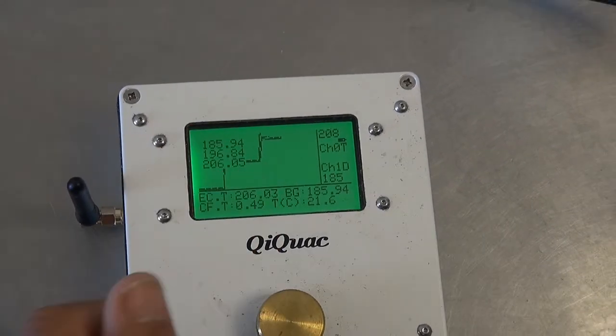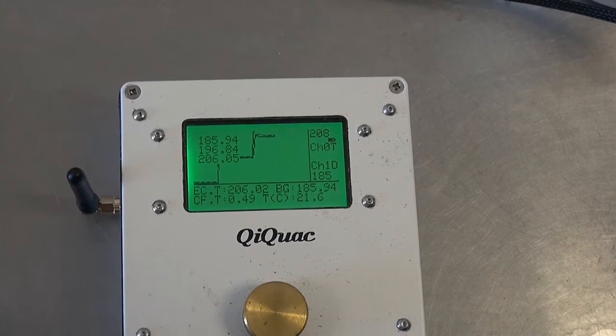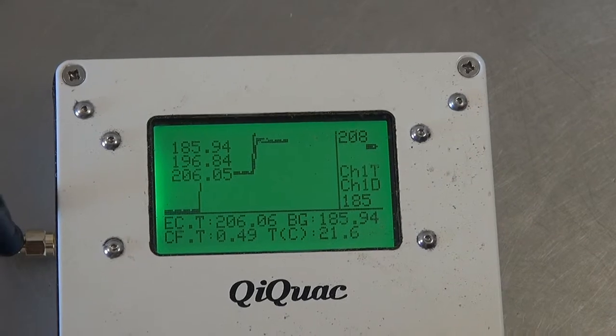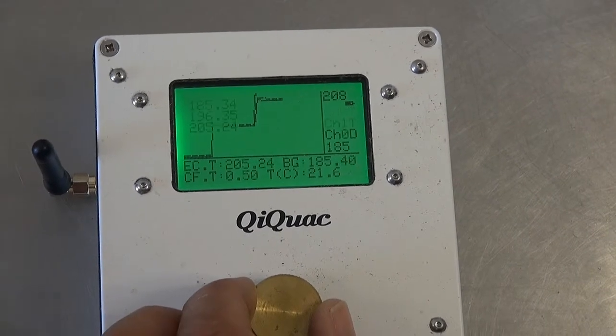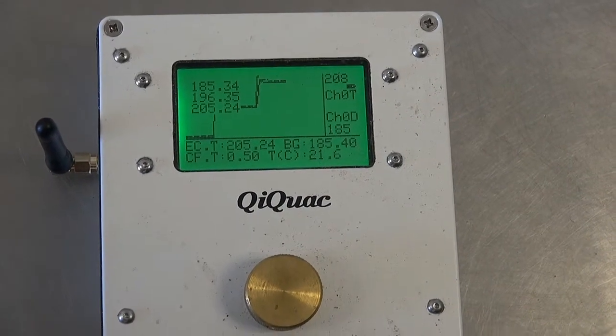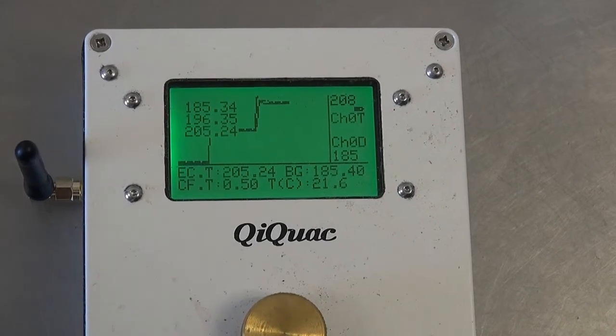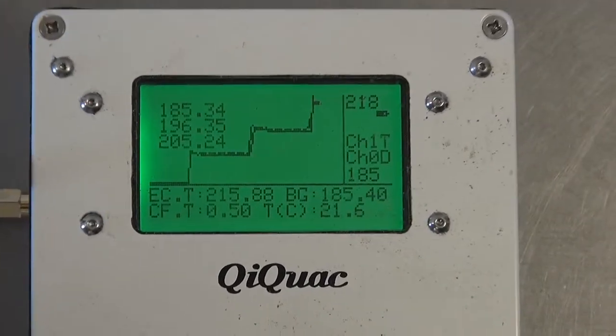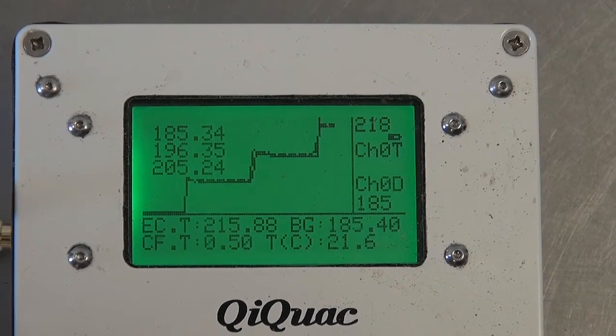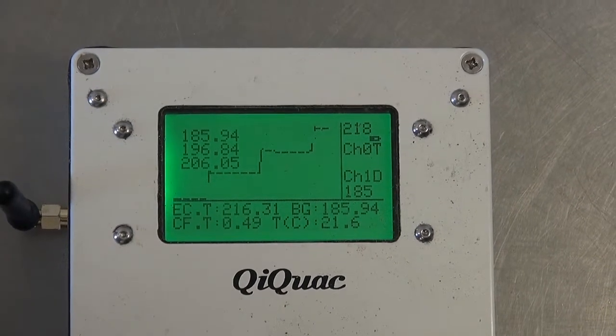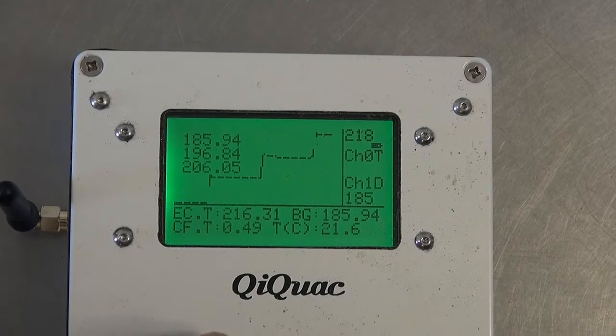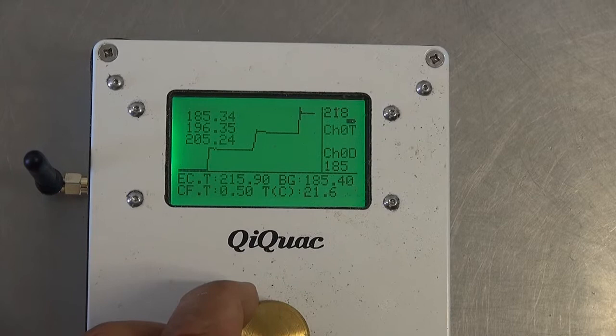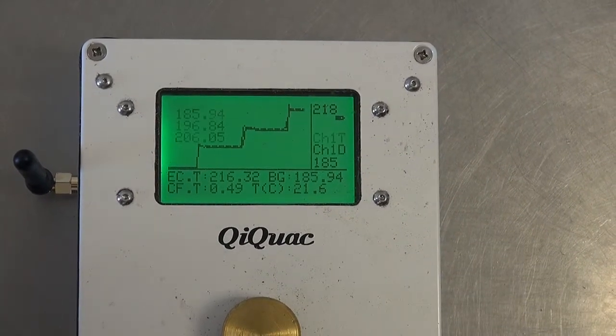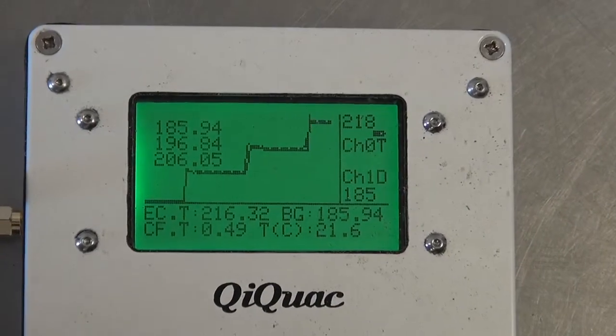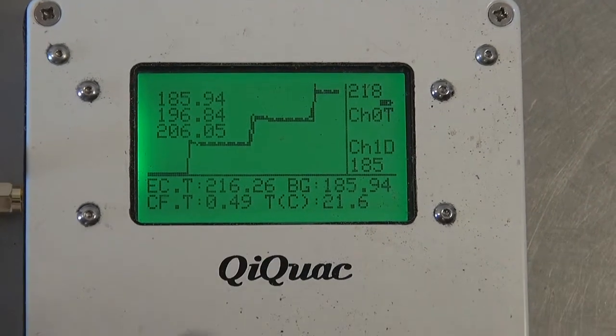Okay, now you see we've got 3 values there. We've got the background, we've got the first injection, and we've got the second injection. And if you look at those values, you can see they're the values for one of the probes. Turn the knob back one toggle, and that's the value for the other probe. And they're both in pretty good agreement, so we'll continue on. And again, we've got the next step up. 215.88, turn the toggle back 1, 216.31. So those are the readings on the 2 probes. Turn the toggle back again, and again, and there we have both probes showing their trace. And again, you can see it's leveled out pretty well, so we'll accept that next value.